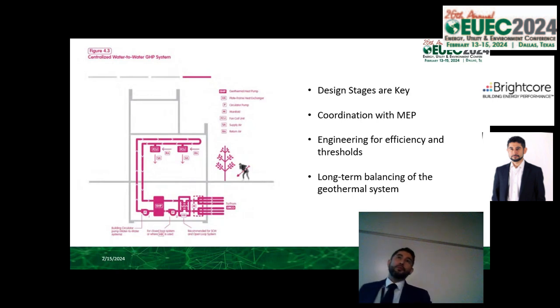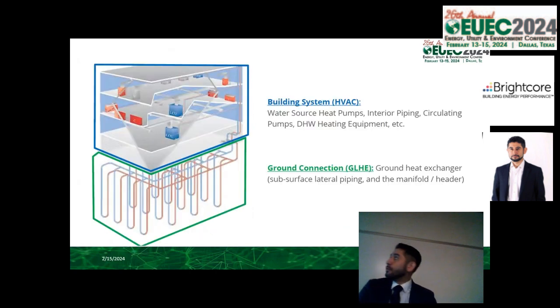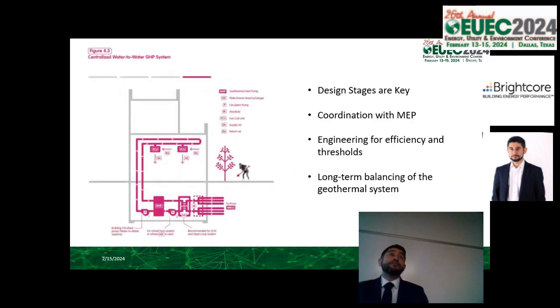Thresholds are important. Previously, say 24 months ago, these did not pencil. The Inflation Reduction Act has provided incentives for geothermal ground loops: a 30% upfront reduction in CapEx, plus another 10% if you use domestically sourced equipment, and another 10% if you're in a disadvantaged community or what's called an energy community—think coal mine areas, oil and gas areas. So you can get up to 30, 40, or 50% off the system in the ground, as well as what some call Division 23, the mechanical engineering distribution systems connected to that ground loop. So for retrofits or new builds, this has become, in some cases, the most cost-effective solution.